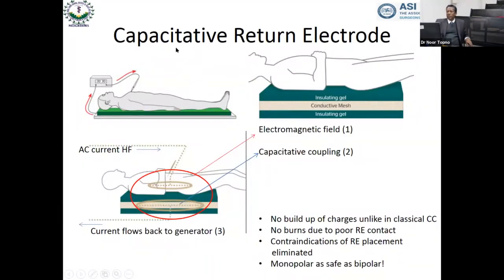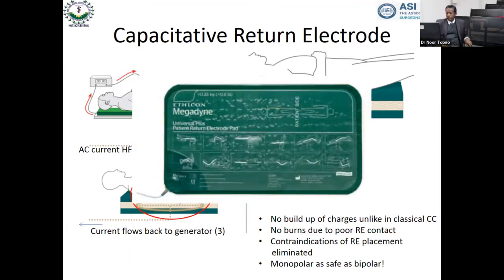Now, capacitive coupling is something that is detrimental to surgery, but it also has some very useful use as far as newer technology is concerned. So here by capacitive coupling, what is happening is the current, here you don't actually have a direct contact with the patient's electrode. The patient is on an insulated gel, and between this conductive mesh, both sides we have gel. The current actually jumps from here to here because of capacitive coupling. So here, it does away with the need of putting any return electrode. So there is no chance of any return electrode burn happening at all. This is how it looks. It is quite a big thing, almost about 2 feet by 1 foot in size.